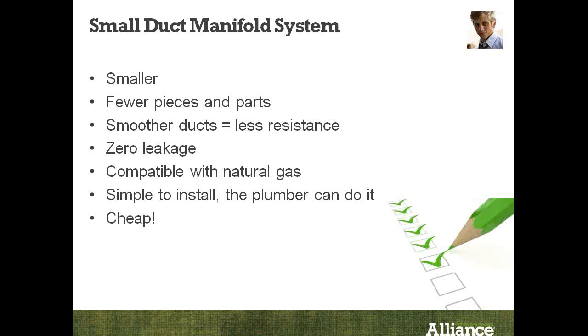Yeah, so just a quick recap on that system we talked about. The system is smaller. We envision this to be able to fit in a floor cavity or a very small bulkhead. And because you're able to bring the ductwork into conditioned space and it's in a centrally located closet or bulkhead, the length of your duct runs can be much, much shorter. So it's a smaller overall system, with fewer pieces and parts. Like we talked about before, if you have one 90-degree elbow, one diameter of duct run, and a couple of other fittings, you could build an entire system with maybe 5 or 6 different pieces, different SKUs.